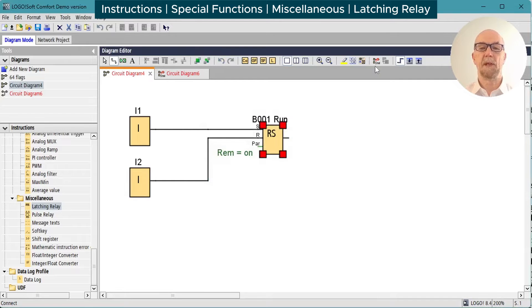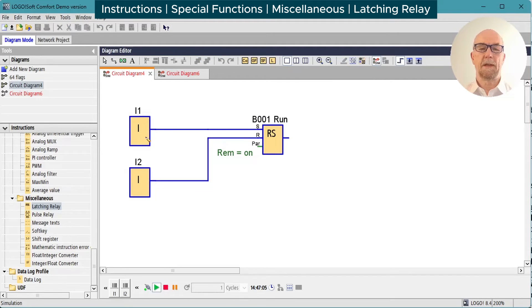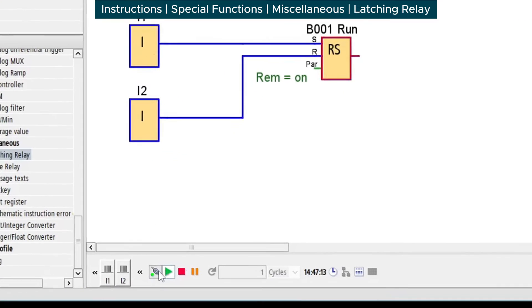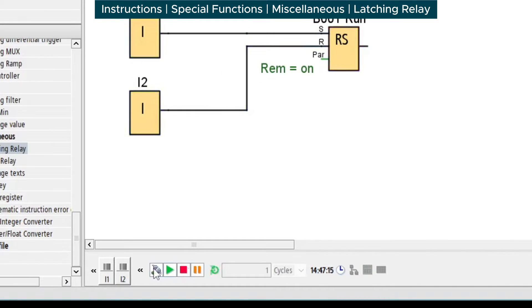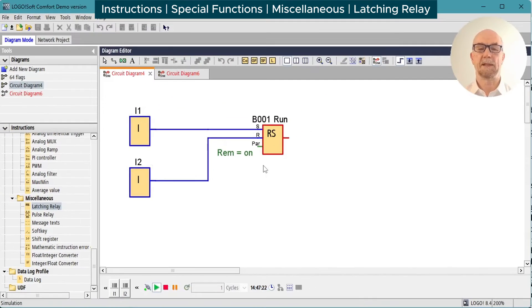Run the simulation. We'll give the set input a pulse. The latching relay turns on. Give the reset a pulse. The latching relay turns off. We'll turn it on again and interrupt the power. Everything goes black. Release the power reset and it has remembered its state because we have retentivity set on.